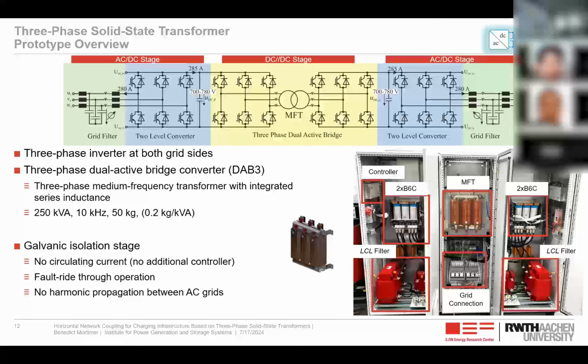So this is a prototype that we have. We use a three-stage converter with conventional three-phase inverters and LCL filters at each grid connection site. And both inverter stages are then connected by a three-phase dual-active bridge, or DC to DC conversion stage. And within this DAB, we use a medium frequency transformer with integrated series inductance, which you can see here in the picture. This component has a rating of 250 kVA, 10 kilohertz, and weighs only 50 kilograms.